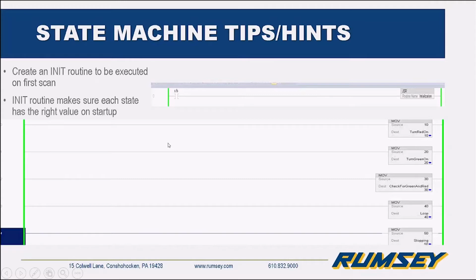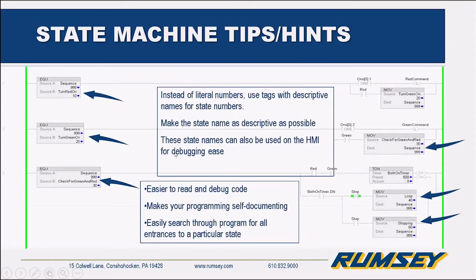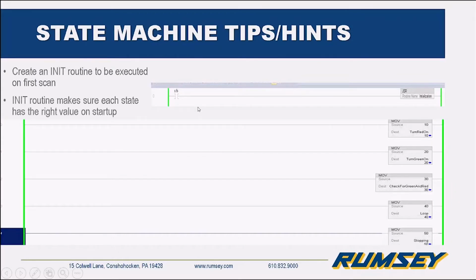When you do that, create an initialization routine to pre-populate those tags with the appropriate values. So upon startup, move numbers into those individual tags once per startup. In case they get overwritten, perhaps someone is back in the previous screen troubleshooting, trying to manipulate the state, and they happen to put a 12 in turn green on, it will always revert back to the original values through this initialization routine.